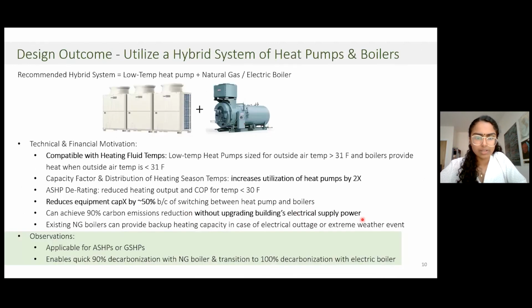So just as a summary of the elements that lead to this hybrid system, we found that when we look at the technical requirements of retrofitting an existing building, we can actually achieve these technical requirements in a way that is cost efficient when we use a hybrid system. We noticed that they're compatible with the heating fluid temperatures that are required for existing buildings. We've also noticed that we can increase the utilization of heat pumps by 2 times. We can reduce the equipment capital cost by roughly 50%, and we can achieve this 90% decarbonization without upgrading our building's electrical supply. I just want to note that this strategy is applicable for both air source heat pumps and ground source heat pumps.